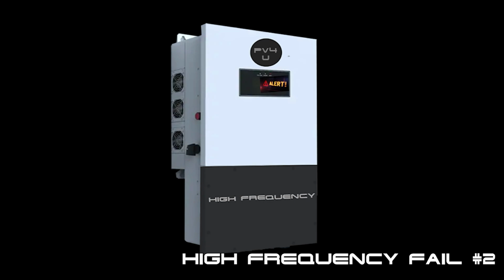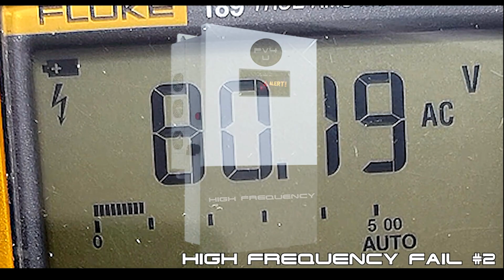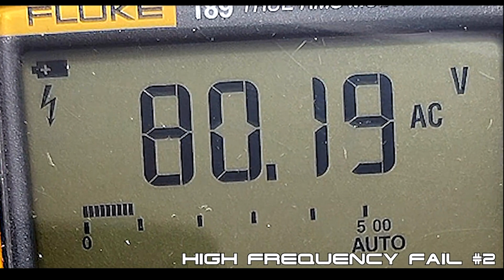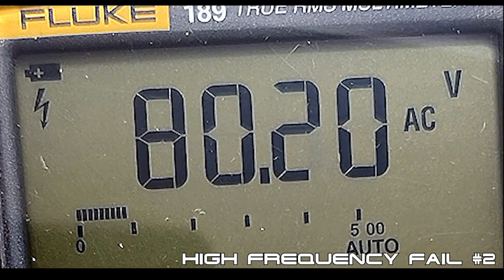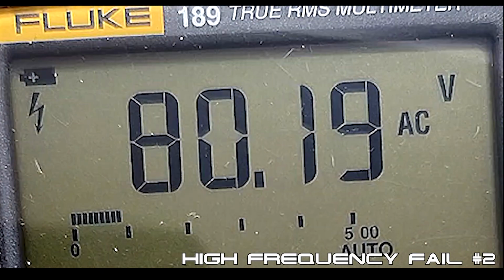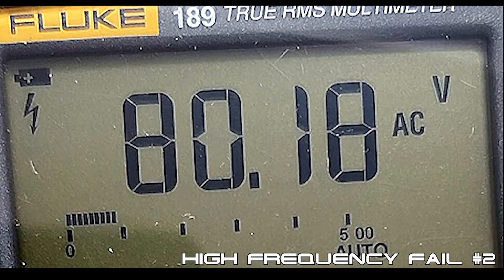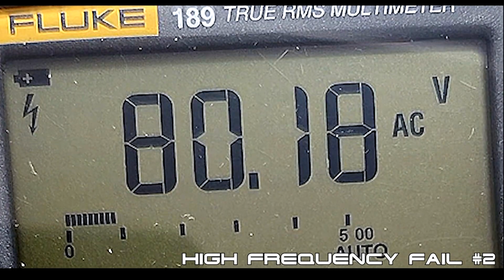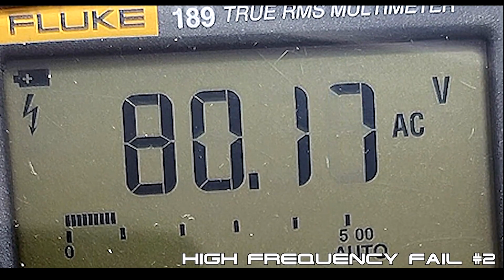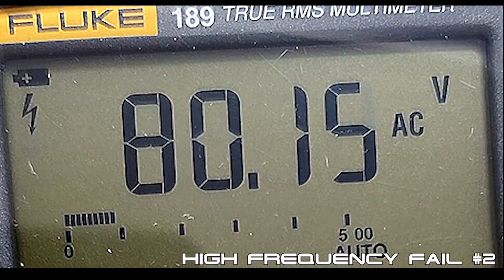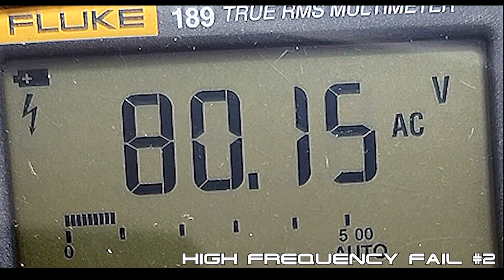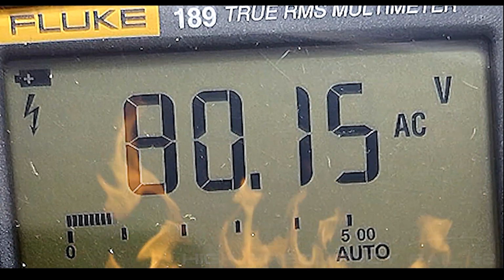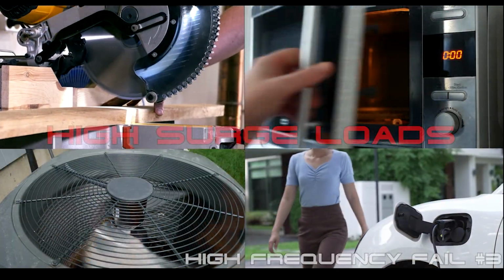Another major issue with many of these high-frequency solar generators and inverters is their overload protection. Rather than shutting down the inverter's output during an overload, most of these inverters will lower their output voltage to as low as 80 volts AC and then slowly ramp the voltage back up, which effectively creates a brownout. The problem with a voltage brownout is that in order to maintain the load's power draw, the load will cause an increase in the amount of current that is drawn, which can damage the windings of electric motors and the insulation of wiring in your appliances, which can eventually lead to short-circuit-induced fires in your electronics and appliances.